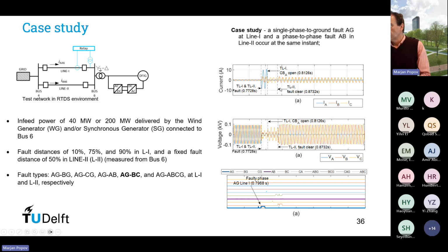Normally, we need to remove it ourselves because we don't have a relay. However, what is important to see here is that the relay operates on a fault that is a single phase to ground fault in its zone. However, it does not operate on the other zone. So we see here also that the faulty phase selector correctly determines the faulty phase.